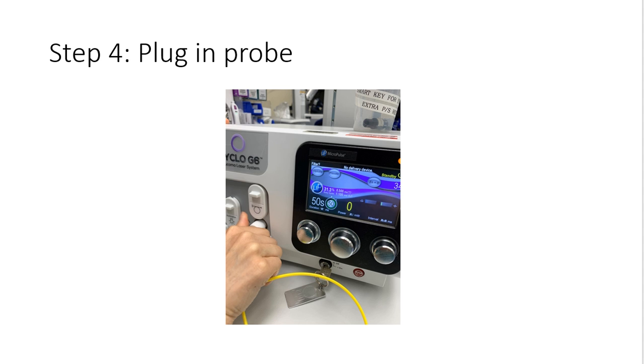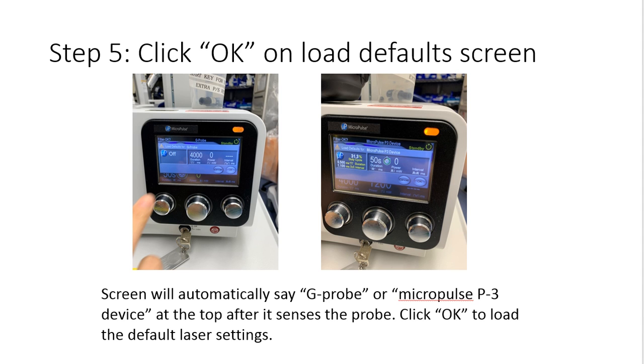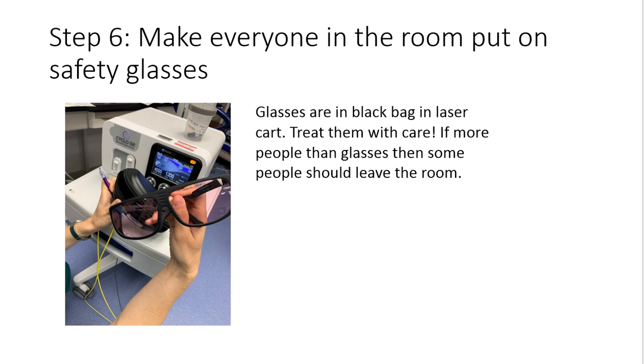So after turning on the laser, you want to plug in the probe in the port shown right here. When the probe is plugged in, the screen should automatically read the probe and either say G probe at the top or micropulse P3 device at the top. When that screen pops up, you want to click OK to load the default laser settings.